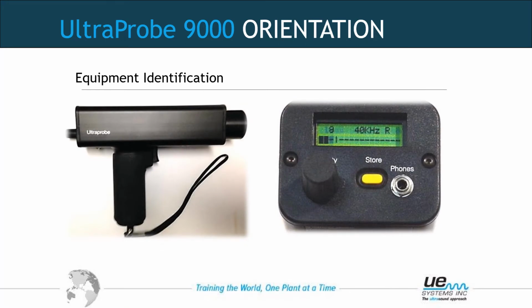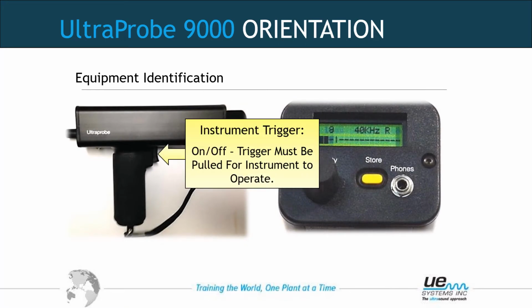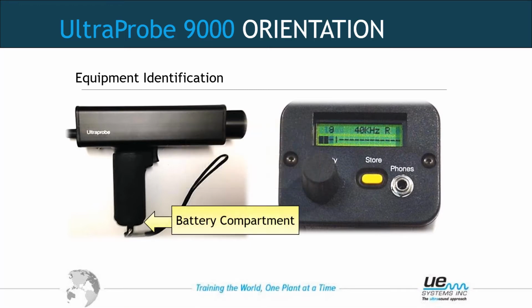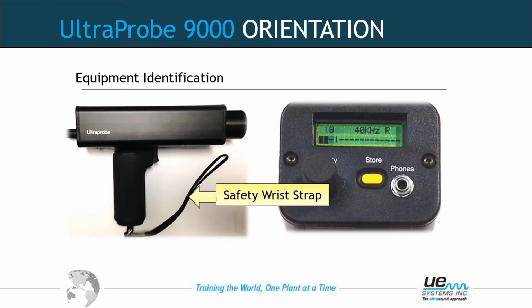Let's identify the different parts of the Ultraprobe. The trigger. It's an on-off trigger. The trigger must be pulled for the instrument to operate, meaning you must hold the trigger in to keep the unit on. If you release the trigger, it will go off within 5 seconds. This cannot be changed as far as the trigger operation. The battery compartment. There is a nickel metal hydride battery in the compartment that stays in the compartment to charge. The battery is charged through the Ultraprobe. The safety wrist strap, as mentioned before, must be worn for safety. Do not let it dangle, as it may cause a hazard toward rotating equipment and electrical equipment.